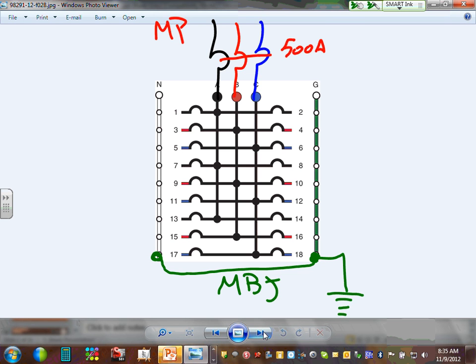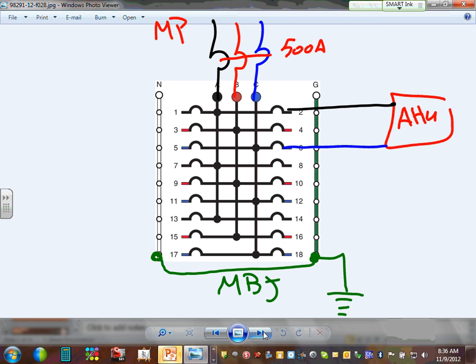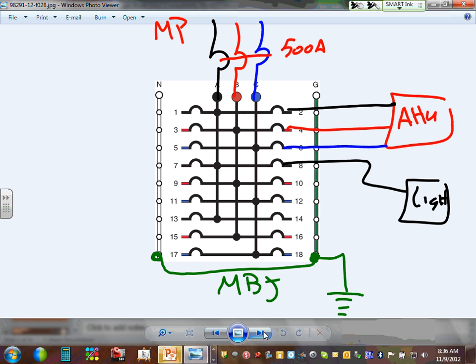If I need a 3-phase load, so here's my air handling unit. I want to color code them. I have my black, and I have my blue, and I have my red. Do I need a neutral for that one? No. If I need a lighting circuit, let's say a lighting circuit. Here's a light. So I need to take it from this circuit, black. And what do I need?